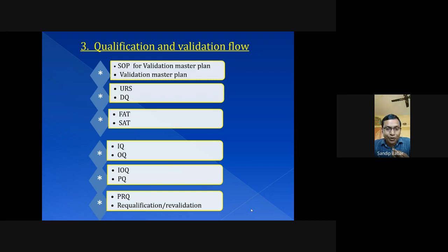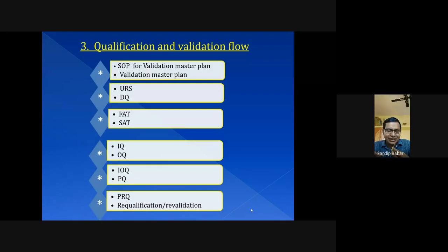For tabletop equipment like pH meter, conductivity meter, spectrophotometer, this design qualification document is not applicable because these are laboratory equipments. They are of fixed design. They will not change as per our requirements. So they don't have a design qualification document.